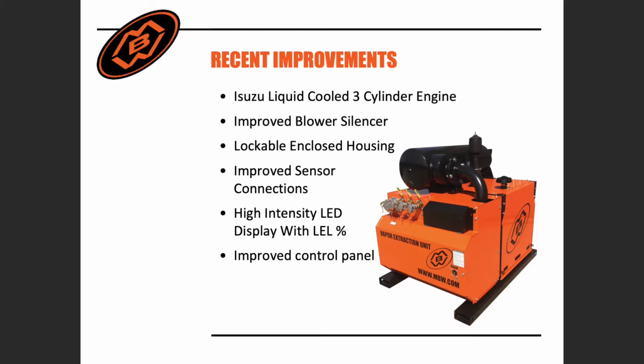The lockable housing allows you to leave the VEU run and not have to worry about someone coming around and messing with it. The plug connection for the VEU has been improved over time. The connections on the first generation VEUs used to break, and we resolved that issue with a universal plug in for the VEU sensor, which improved the connection tremendously. We no longer have any sensor connections breaking.